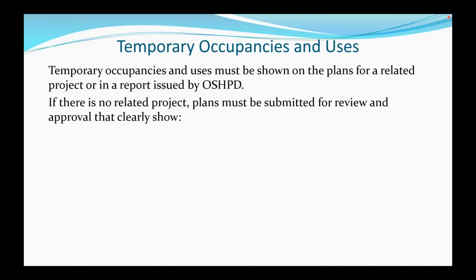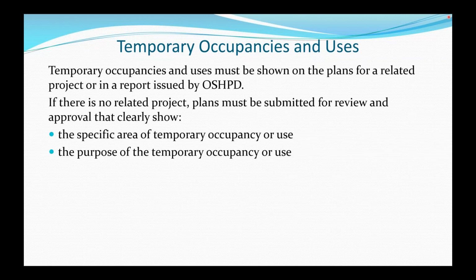Okay, let's get into temporary occupancies and uses. These must be shown on the plans for a related project or in a report issued by OSHPD if need be. If there's no related project, plans must be submitted for review and approval that clearly show the specific area for temporary occupancy or use. And this is when you'll get into like a flu season and you want to put in a temporary flu clinic or an area to house people. It still needs to be looked at and approved by OSHPD.